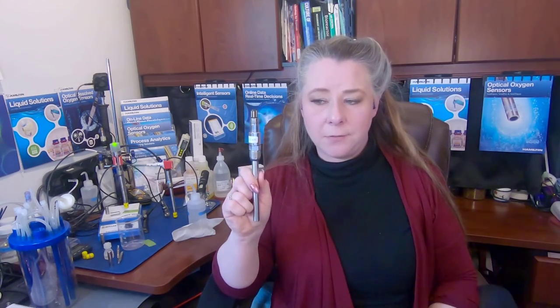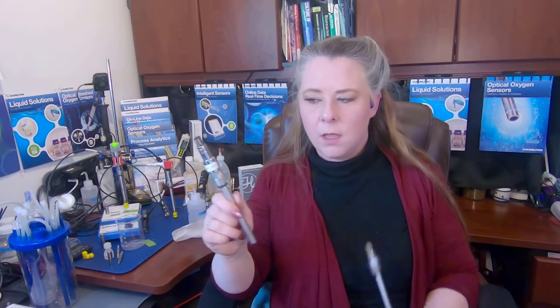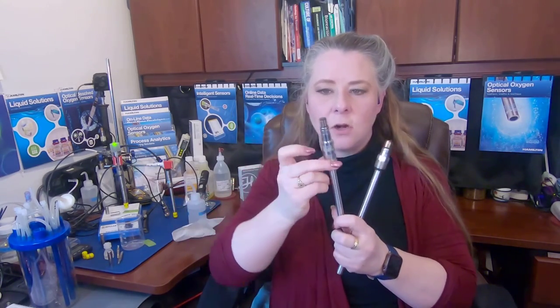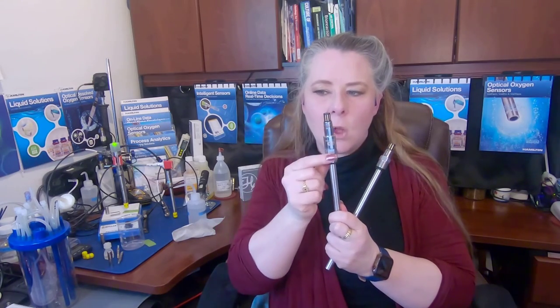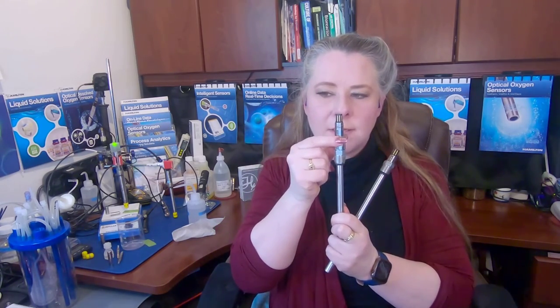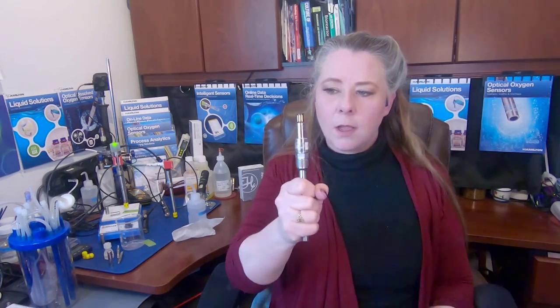The first kind of calibration we're going to talk about is calibration of the sensor itself. This is only possible on intelligent sensors, which are generally optical. Intelligent sensors like this, it's an arc sensor, actually hold the calibration and copy it into the head of the sensor. So I can calibrate this, put it on a shelf, grab it later, autoclave it, and then put it on any bioreactor and it will see the calibration and read it from the sensor. That's awesome. It saves me time. It means I can get rid of that 13% possible error.